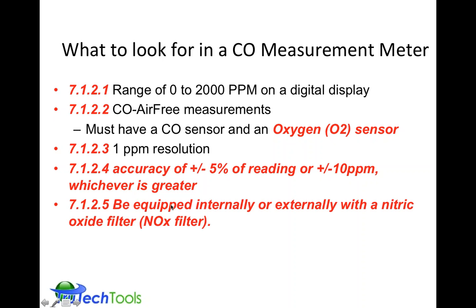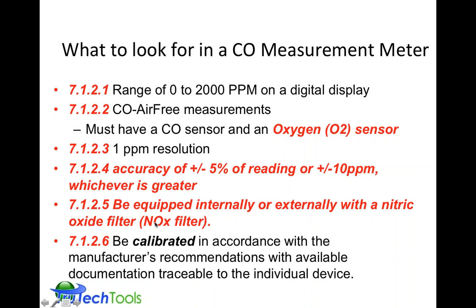Another restrictive requirement: it must be equipped internally or externally with a nitric oxide or NOx filter. And we'll explain in a minute why that's important. It must also be calibrated in accordance with the manufacturer's recommendations with traceability of the calibration. That's usually not too hard of a hurdle for a combustion analyzer, but it's these things with the oxygen sensor, the accuracy, and the NOx filter, which will restrict or limit some brands and models of combustion analyzers for this part of the standard.